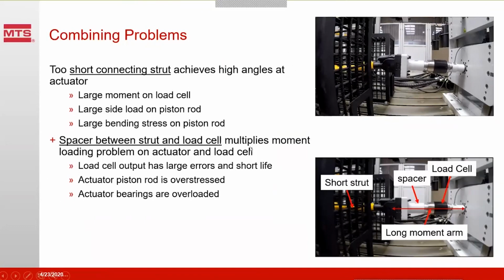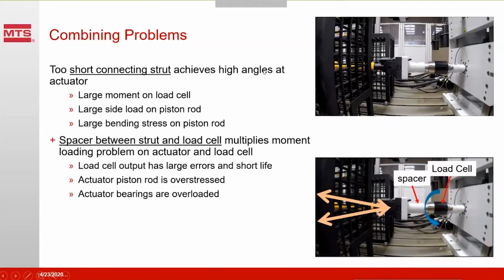Spacer between the strut and the load cell multiplies the moment loading problem. So the load cell output has large errors and short life. This is a big moment arm that's going to get a fairly high angle with that short strut. Well, what are some ways we can address that problem? This is our short strut example here in the bending load.